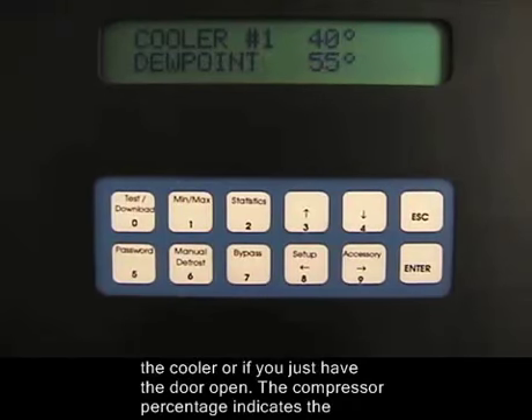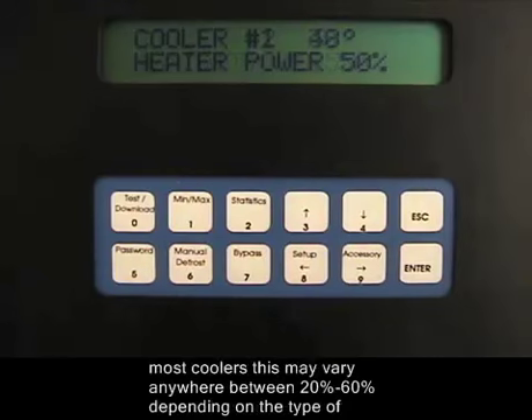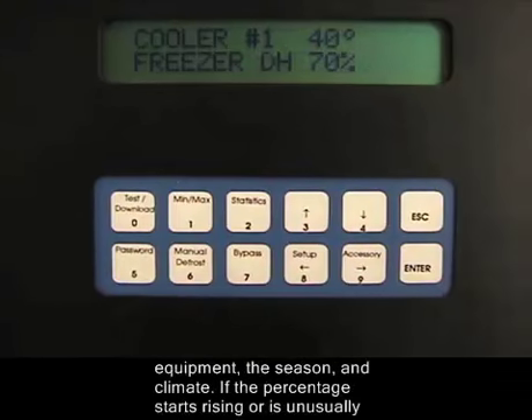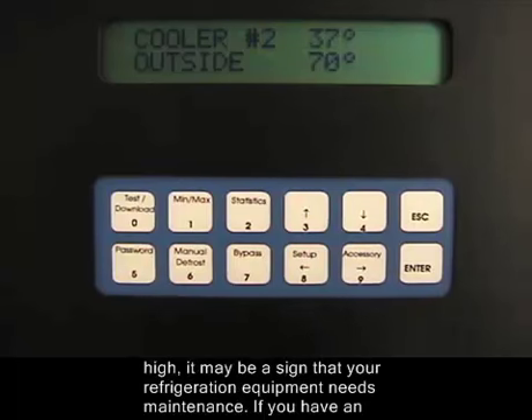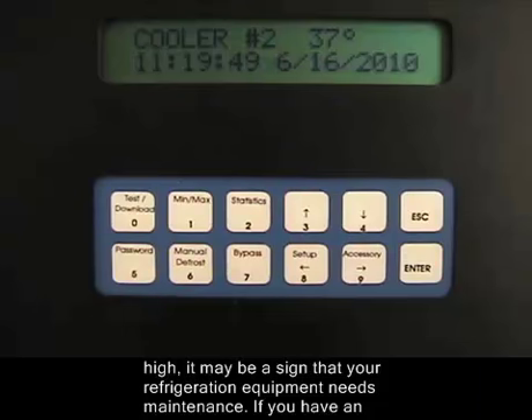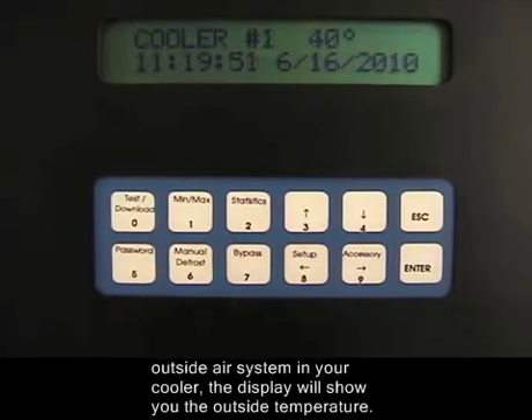The compressor percentage indicates the percentage of the past 24 hours that the CoolTrol has been calling for refrigeration. For most coolers, this may vary anywhere between 20 and 60%, depending on the type of equipment, the season, and climate. If the percentage starts rising or is unusually high, it may be a sign that your refrigeration equipment needs maintenance. If you have an outside air system in your cooler, the display will show you the outside temperature.